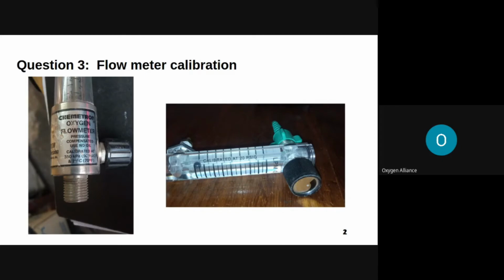Another thing to look into is the maximum flow reading of the flow meter. It's not recommended to place a 10 liter per minute flow meter on a 5 liter per minute oxygen concentrator, because this can lead to low oxygen purity, as the concentrator is designed for a maximum of 5 liters per minute. Going above 5 liters per minute will kill the performance of the oxygen concentrator. Vice versa, a 5 liter per minute flow meter cannot be placed on a 10 liter per minute concentrator. Why? Because the oxygen concentrator will not be able to perform to its fullest. So you need to make sure that you put in a 10 liter per minute flow meter for a 10 liter model. Otherwise, you won't get the whole performance of that particular oxygen concentrator.